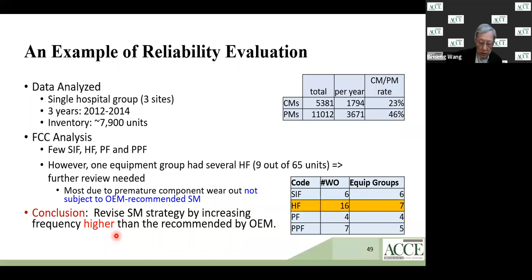But the failure rate was higher because we found out that in this particular place, the environment was very dusty, and the molecular sieve bed that is used to sequester nitrogen and therefore concentrate oxygen was getting dirty quicker than expected. The manufacturer recommended replacement every 10 years, but every 5 years we were starting to see deterioration of the oxygen concentration. So actually, when you perform evidence-based maintenance, you may end up concluding that you have to perform maintenance at a higher frequency than that recommended by the manufacturer. You're not always saving money and saving time.